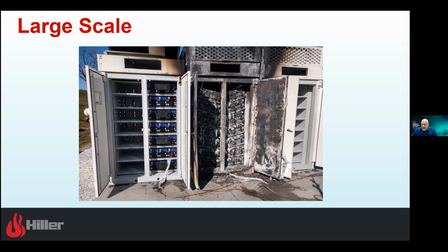What I'll say is the presence of a fire suppression system, as you pointed out in your picture there, could actually present a significant issue if you are essentially sealing up the enclosure to allow an aerosol agent to work, you're not removing those gases. So I think there's some conflict in the codes, allowing a clean agent system and potentially requiring a deflagration prevention system as well. I think that's something we hope to address in NFPA 855.